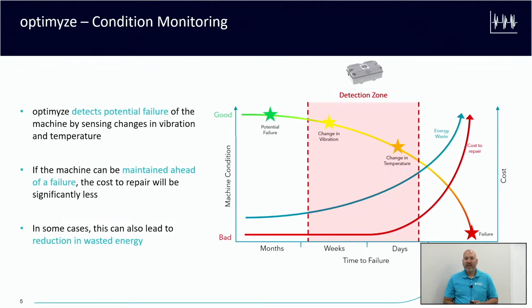So here we have a PF interval chart, just kind of giving you the whole ideology behind the optimyze sensor or condition-based monitoring solutions. So P stands for potential failure. That's that green star. A brand new product may be anything to the left of that green star. We know it's perfectly healthy. The components are good. It's going to operate. But over time, it starts to slightly deteriorate, and that would be any point to the right of that green star, right? It is starting to wear a little bit. But we still have months, weeks, days for the product to operate.